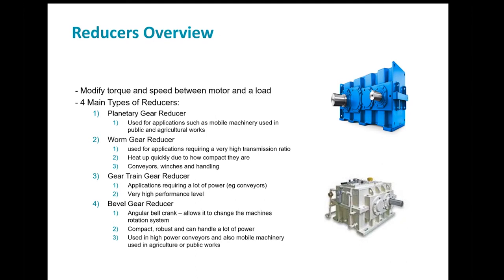When should you use a planetary gear reducer? Planetary gearboxes are compact. The advantages include compact size, high efficiency, low clearance, and high torque-to-weight ratio. But due to their design, they require very specialized maintenance.